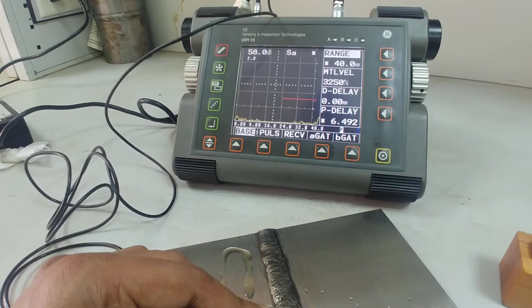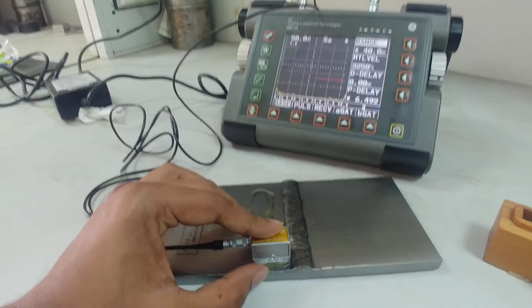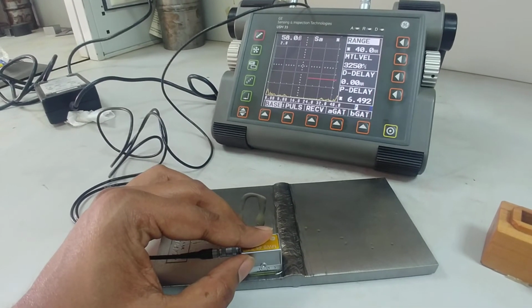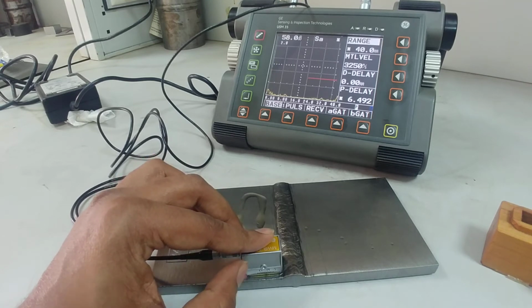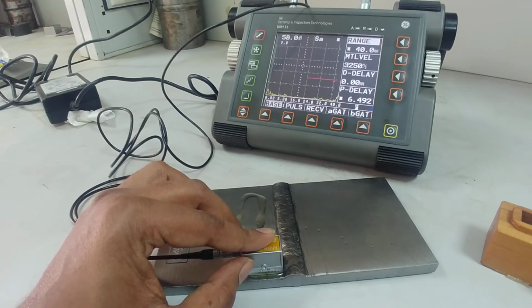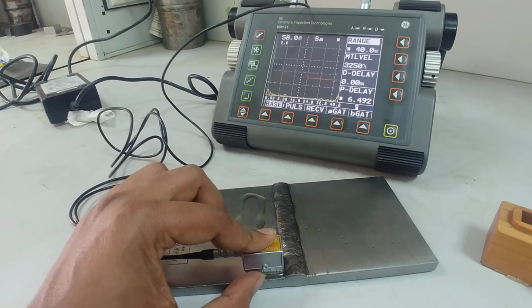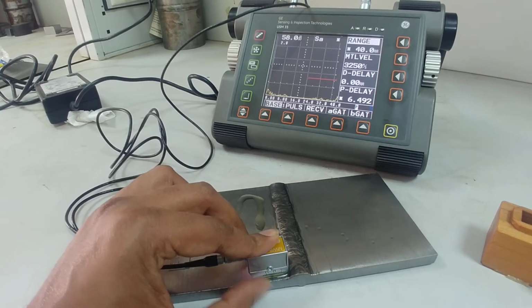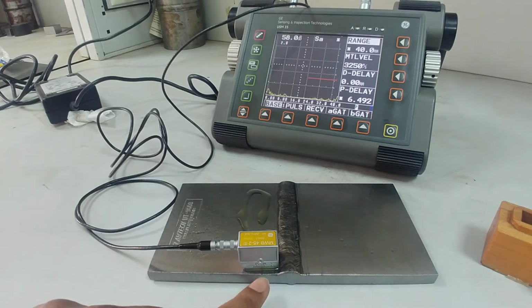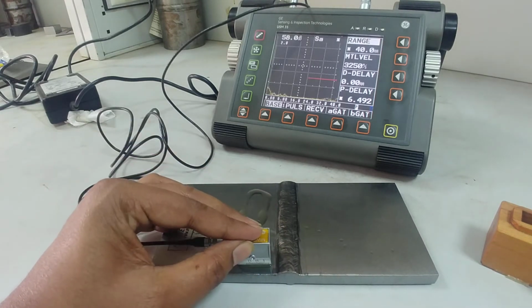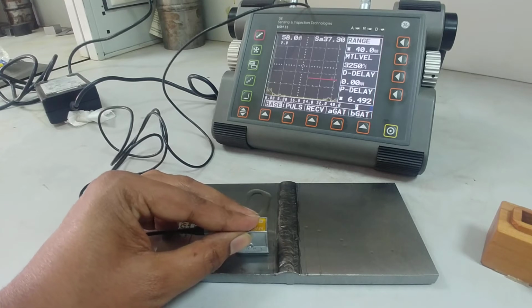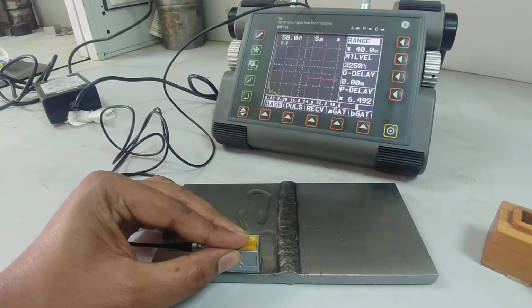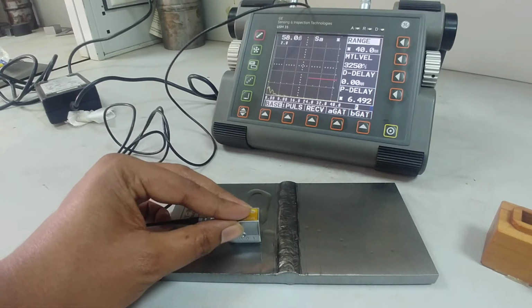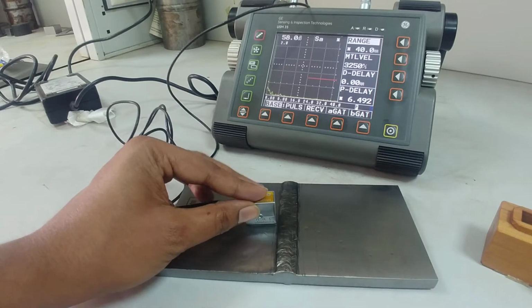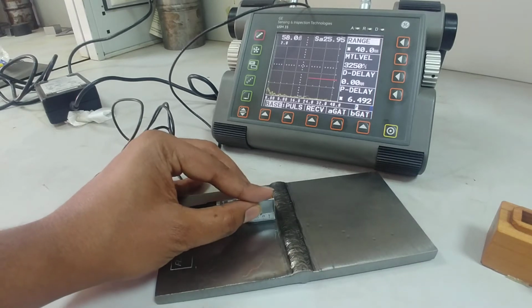You can see why we don't use a small angle probe. It's a very good example, because the maximum I can go is, you can see the start point, I can go to full half skip distance. I cannot go beyond that full skip distance. This is the line for full skip distance, and I cannot reach beyond it. That's the reason why we don't select small angles for thin plates. You can see I hardly get any signal because I cannot cross it.